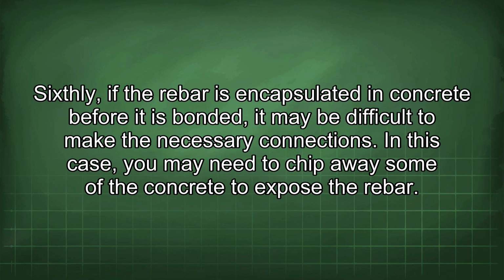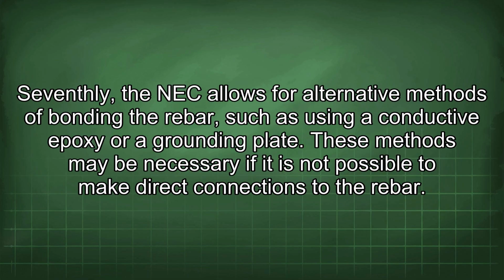Sixthly, if the rebar is encapsulated in concrete before it is bonded, it may be difficult to make the necessary connections. In this case, you may need to chip away some of the concrete to expose the rebar. Seventhly, the NEC allows for alternative methods of bonding the rebar, such as using a conductive epoxy or a grounding plate. These methods may be necessary if it is not possible to make direct connections to the rebar.